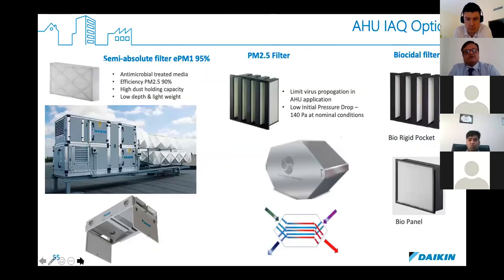Next slide, please. So when we look at the air handling unit, definitely the filtration grade can be upgraded, so MERV 14 is possible if it is possible. Generally, if you have a motor with an EC fan, or you can upgrade to an EC fan, you can adjust the static pressure, because higher filtration will definitely add to the static pressure loss. So once that adjustment is done and you go for a higher level of filtration, you are getting better air. Biocidal filters, possible in biopanel with charged enzymes, would be a way to go forward.